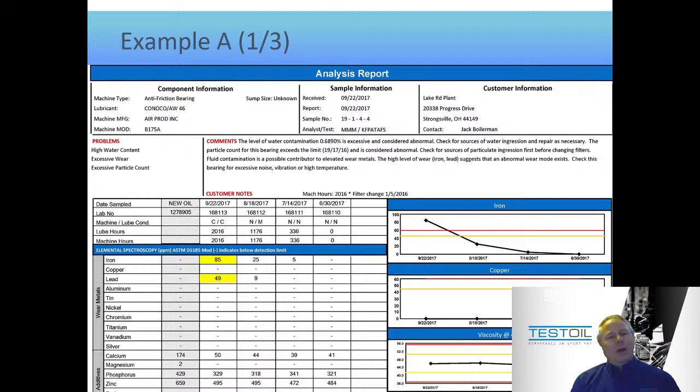So then people say, but wait a minute. That may stop more from getting in, but you clearly have too much there already. So they start saying, why don't we add filtration? And they go, well, that's a great thought. I said, give me a micron rating of a filter you'd run on this. And sometimes people give me really high answers, like 30 microns or 20 microns even. But let's pretend the answer is 10 microns. So if somebody says, I'd throw a 10 micron filter on that, it would clean everything up. I go, well, will it?